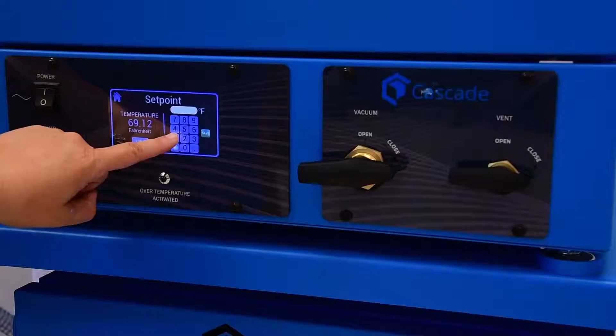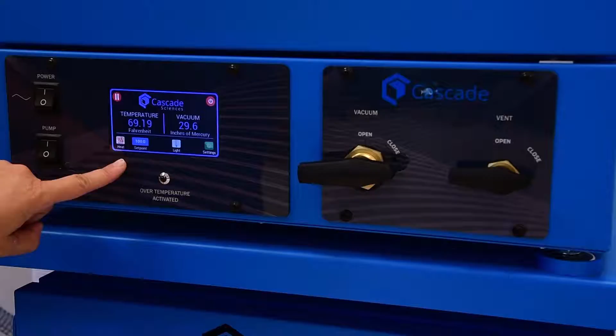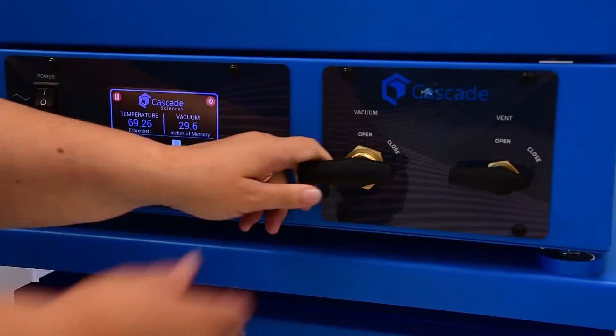So we don't apologize for that at all. This controller controls temperature and displays vacuum. So the vacuum is not a controllable variable on here, it's just for display. The temperature controller also has an integrated high limit thermostat, so there is some over temperature protection here, which is fantastic. In the standard configuration, you're going to manage both vacuum and vent from this front panel.